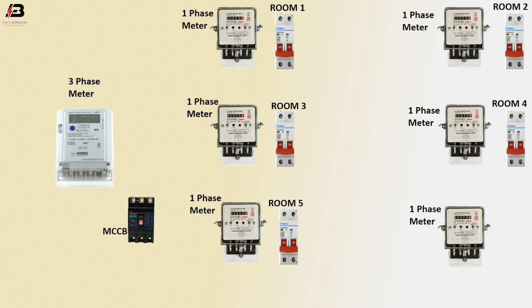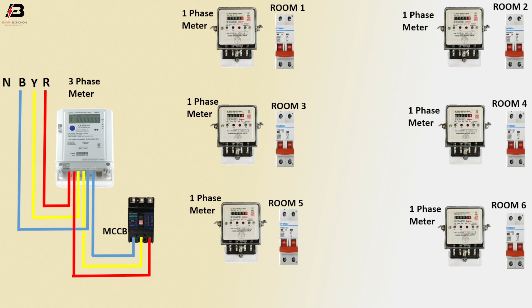First phase connection input to the three phase energy meter. Phase connection output from the energy meter connects to the MCCB circuit breaker. Second phase connection to the three phase energy meter. Third phase connection to the three phase energy meter, then from the energy meter to the MCCB circuit breaker. Neutral connection input to the three phase energy meter, and neutral connection to the room 1 single phase energy meter.